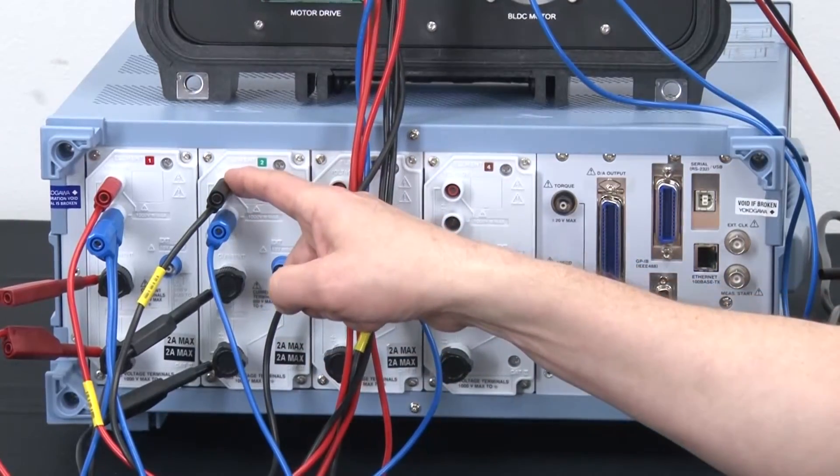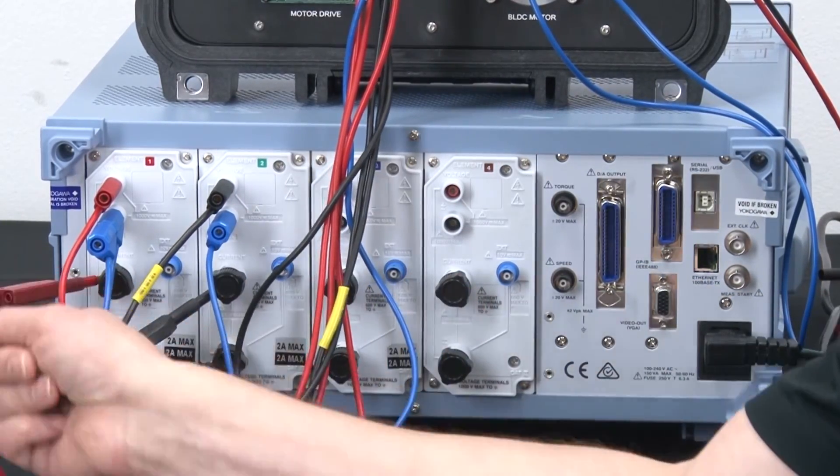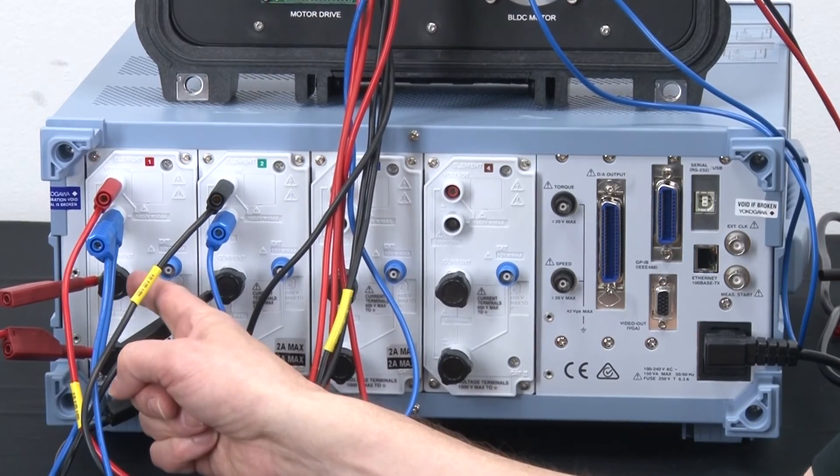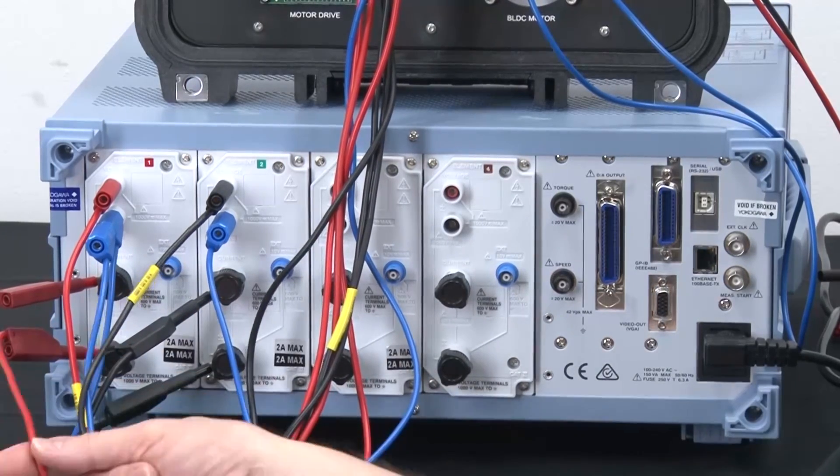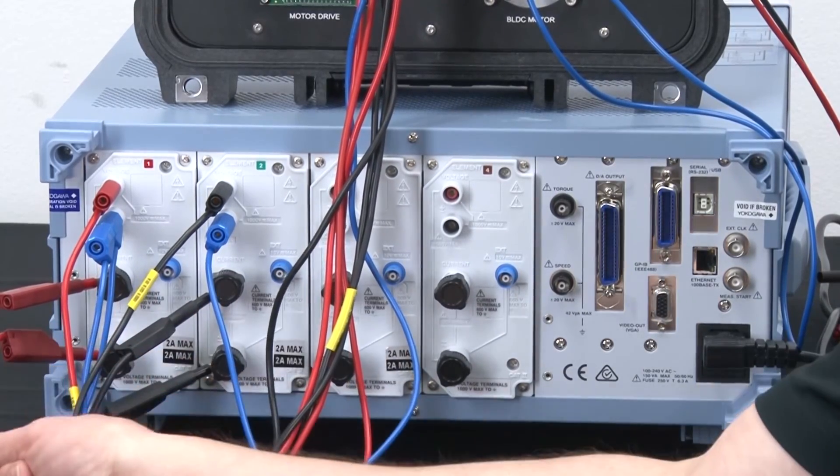Next, on the current inputs, I simply take phase R from the drive and pass it through the top of the internal shunt or the current input on the power analyzer and pass it out the bottom. And then that goes back to the motor. So that's phase R. It's red.